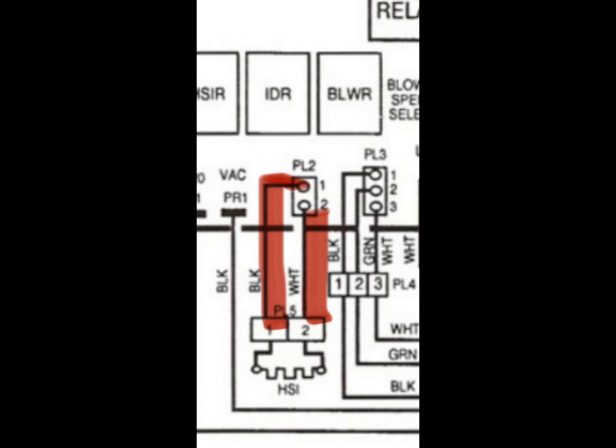I didn't forget about our ignition source—I just kept it for last because it's very straightforward. It's a two-pin plug, black and white. We can see that when we test straight to pin 1, we should have that voltage there when the gas valve is opened. For hopscotching correctly, we've made our way to the gas valve, the gas valve opened—we saw it electronically, we also heard it in the physical. The gas valve opened, the gas is pouring, but nothing is glowing. No hot surface igniter is igniting, there's no spark ignition system, nothing is happening. We can come straight to here, and for a couple moments you're going to see: do you have that 120 volts and then it's gone? Or does it constantly stay zero? If it constantly stayed zero, that board never told it to—we got a board problem. If it gave 120 volts directly to that hot surface igniter and it never ignited, we have to change that igniter out.